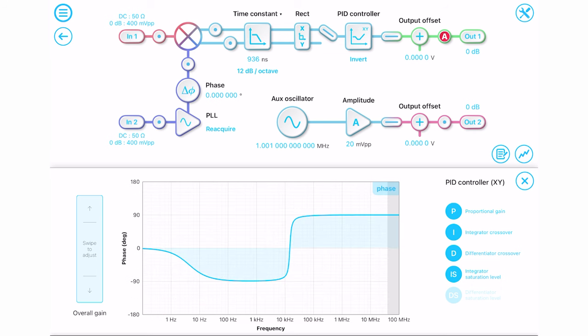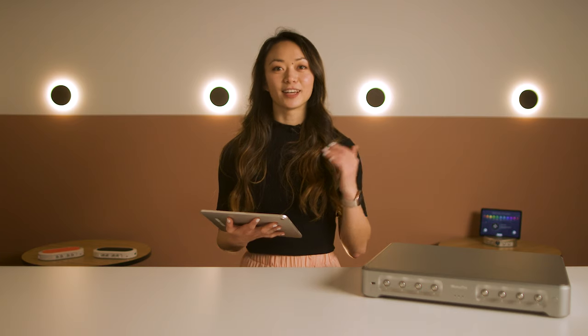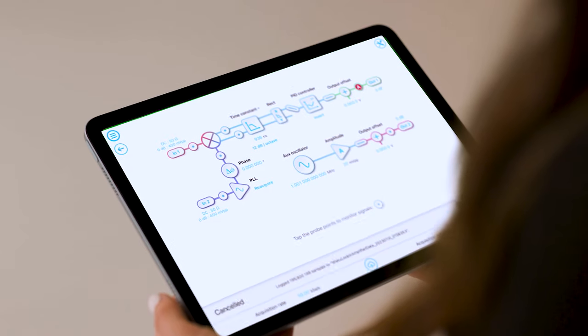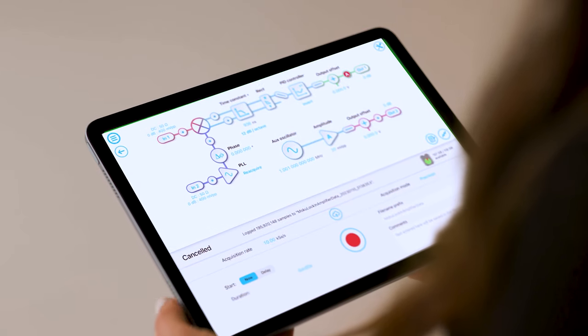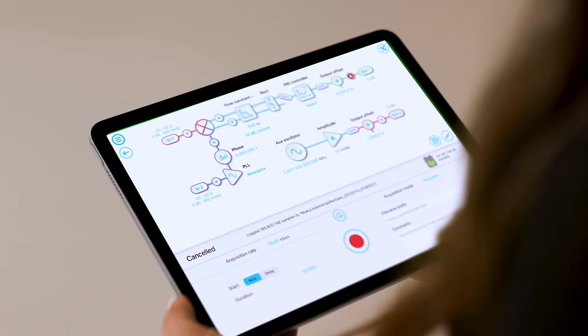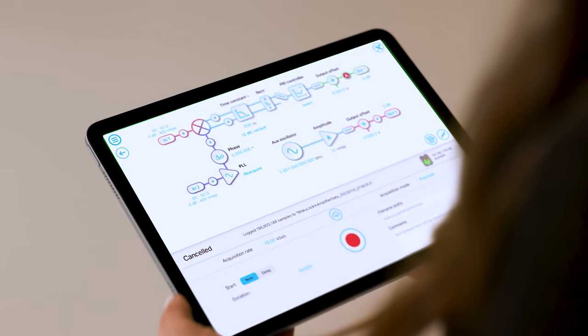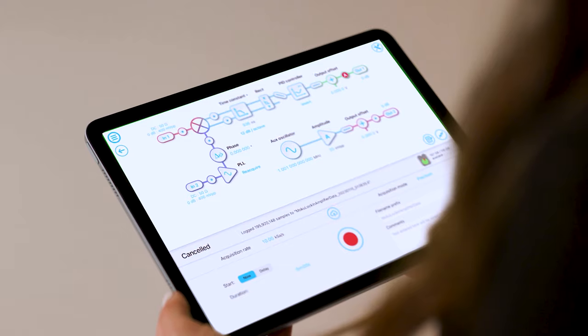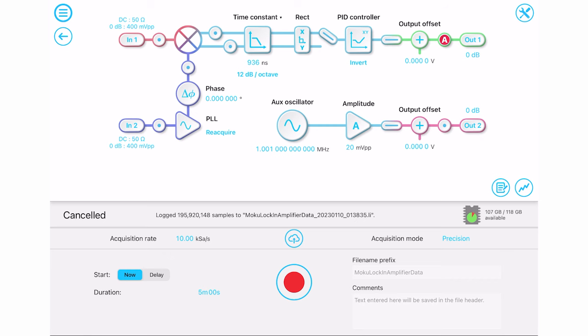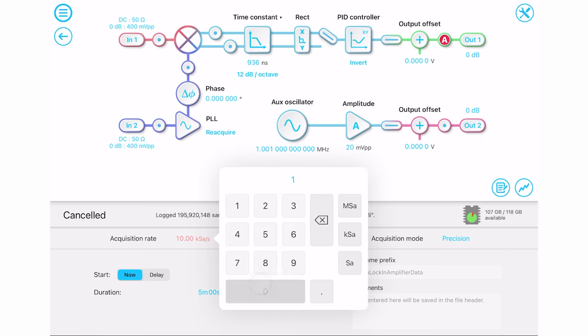If you want to track long-term system performance, you can record the signals at the active probe points with the built-in data logger, which can acquire data at up to 10 mega samples per second.